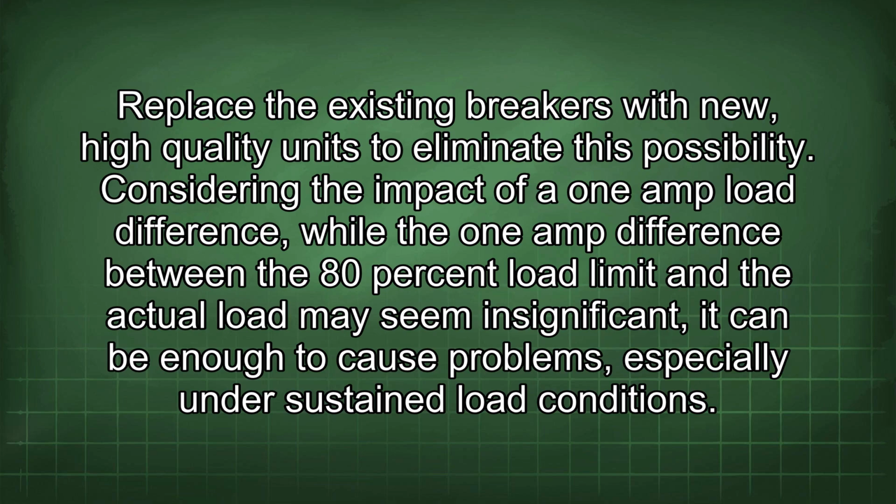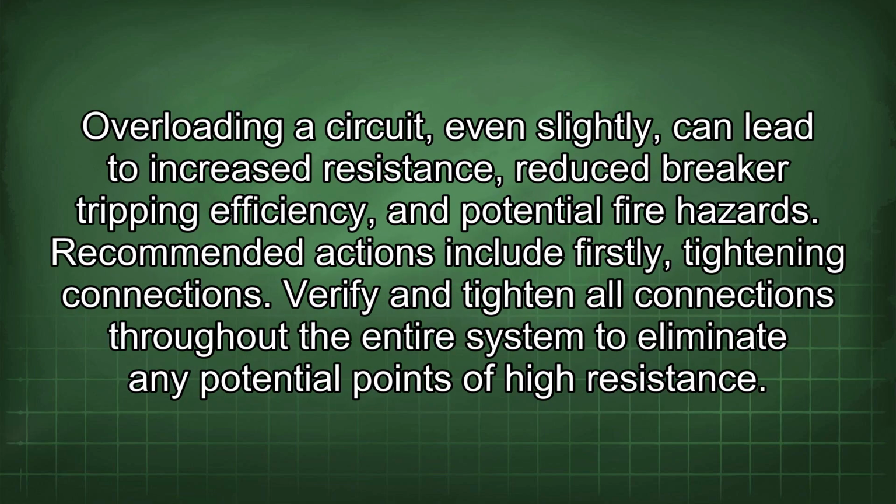Considering the impact of a 1 amp load difference, while the 1 amp difference between the 80% load limit and the actual load may seem insignificant, it can be enough to cause problems, especially under sustained load conditions. Overloading a circuit, even slightly, can lead to increased resistance, reduced breaker tripping efficiency, and potential fire hazard.